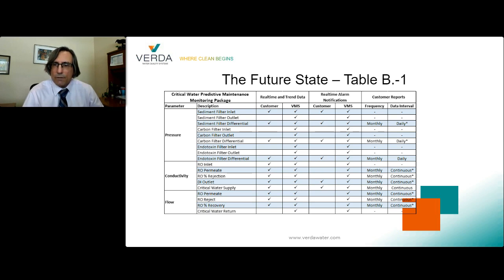If there's a problem like our ultrafilter blowout example and the pressure differential drops too low, an alarm will be triggered. That alarm is a text or an email notification to our techs and in some cases the customer. The sensors allow us to collect and store the data in frequent intervals, like every second if we want. Every month we summarize that data into reports that the customer can review and show CMS and the Joint Commission. In this way, our customers can demonstrate that they are meeting these daily monitoring requirements in the guideline.